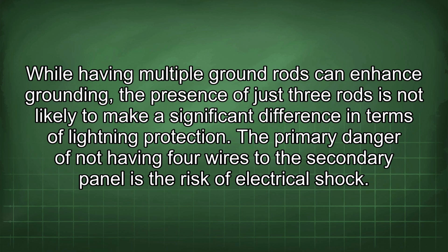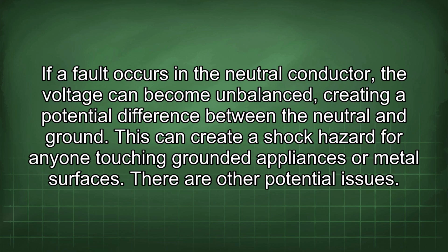The primary danger of not having 4 wires to the secondary panel is the risk of electrical shock. If a fault occurs in the neutral conductor, the voltage can become unbalanced, creating a potential difference between the neutral and ground. This can create a shock hazard for anyone touching grounded appliances or metal surfaces.